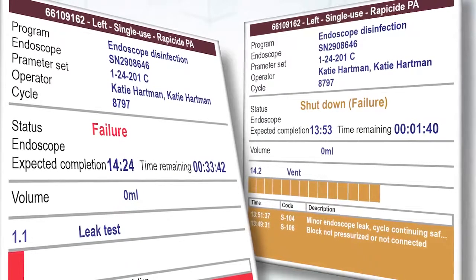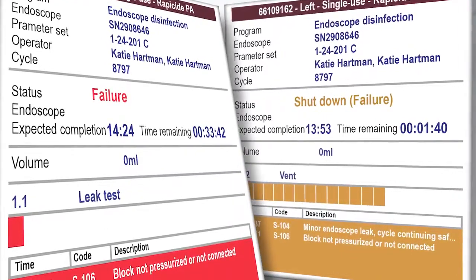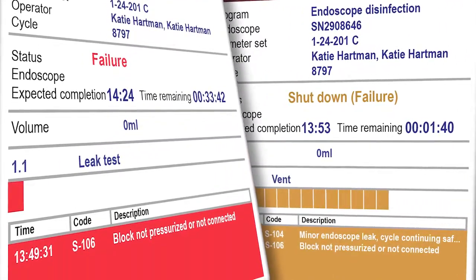Sometimes when a flexible scope is placed in an AER, there can be some issues. For example, the machine may have an error in the readout. Sometimes it's because the connections aren't on tightly. Sometimes it's another problem with the machine and the machine is malfunctioning. Whenever that happens, whenever we have an interruption in a cycle, stop what you're doing, find out what the problem is, and then correct that before you move on.